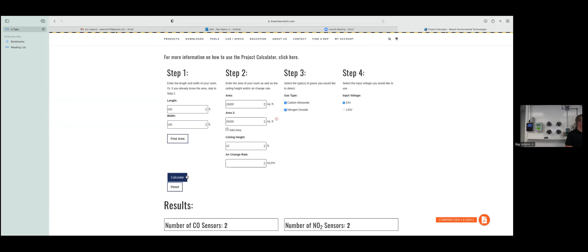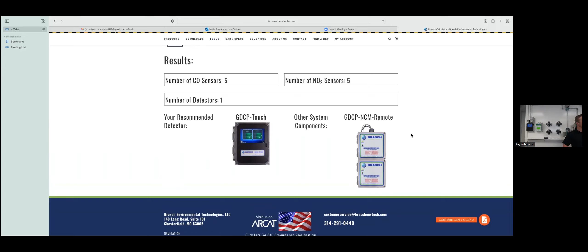Underneath this area mark, for multi-floor parking garages and things of that nature, you can add additional areas in to factor those floors in. As you calculate, it's going to jump you up to the control panel as you now have a total of 10 sensors, which surpasses the 4 sensor limit of the standalone unit itself. So it's just a quick way to take in those parameters, determine how many sensors you may need, and then apply them into the specification itself.